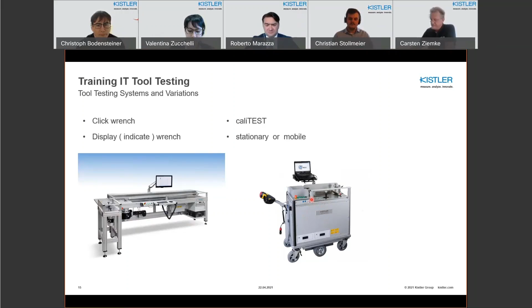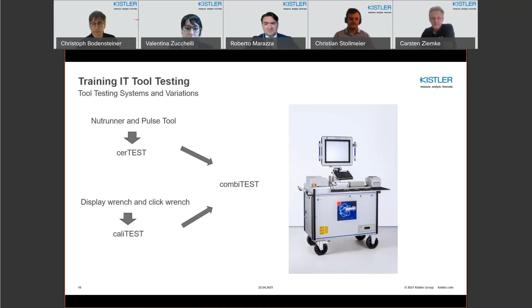For nut runners and pulse tools, we have our cerTEST. For display wrenches and click wrenches, we have our caliTEST. And now, Roberto talked about it, we also have, for both technologies, our combiTEST. The combiTEST has an automatic drive unit to calibrate wrenches, in the standard up to 300 Newton meter, and in a special solution up to 500 Newton meter. And you also have the possibility to build in 4 simulators to simulate the fastening point characteristic for testing nut runners.